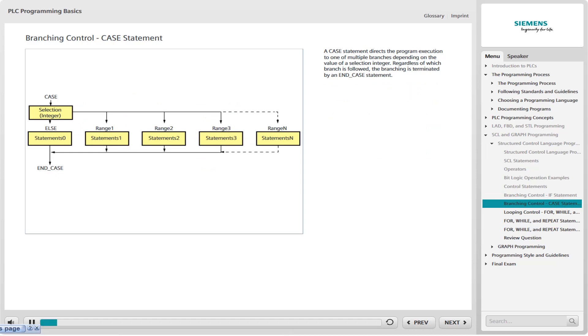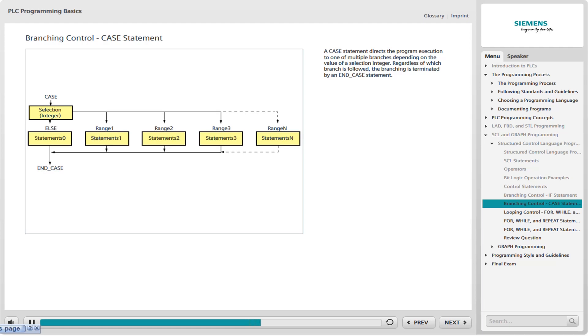The CASE statement directs the program execution to one of multiple branches depending on the value of a selection integer. Regardless of which branch is followed, the branching ends with an END_CASE statement. Each statement group, except for the one preceded by the optional ELSE statement, has a range value or set of values. If the selection integer equals a value within the range for a statement group, that group is executed. If the selection value is not within any range, the statements preceded by the ELSE statement are executed. The range can be expressed as a single integer, integer values separated by commas, a minimum and maximum separated by two periods, or a combination of these approaches.